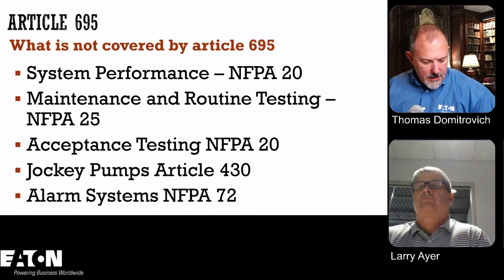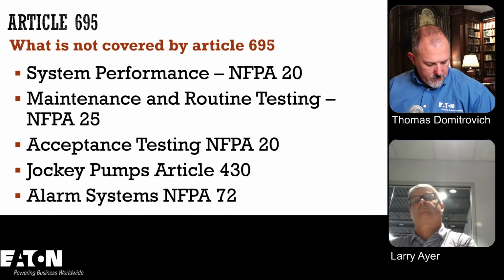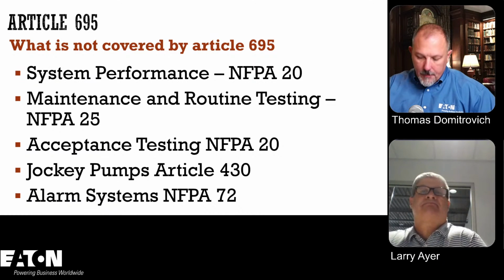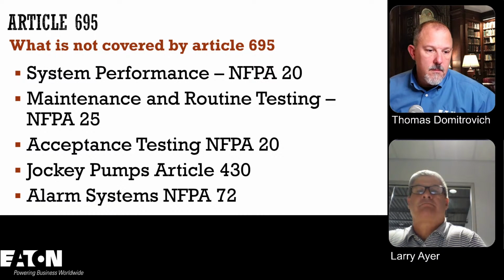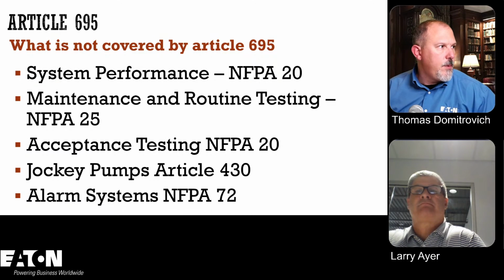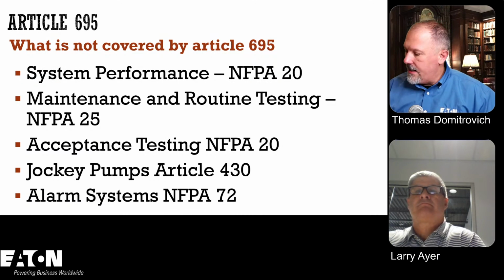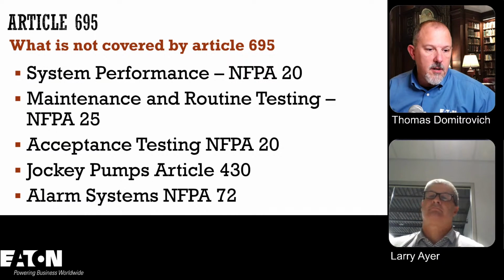Do we have maintenance in 695 at all? I do not think so. No, I mean, we have it in Article 700, but not in 695. Jockey pumps are in Article 430, so we talked about that. And the alarm system is NFPA 72, which I don't think we put on that earlier slide. So NFPA 72 is in there as well from an alarming perspective.